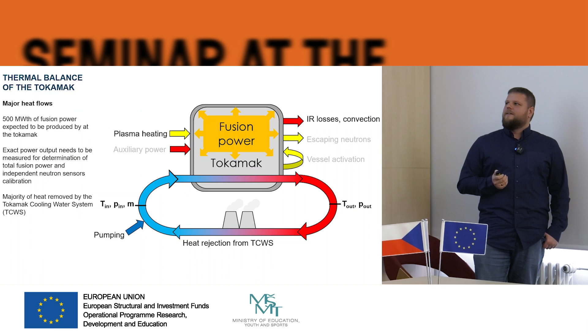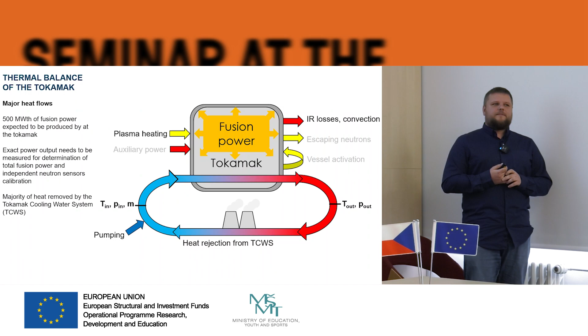The accuracy of neutronic sensor measurements decreases with time, and they need to be calibrated sometimes. In fission power plants, this is done with exactly the same system. You have a completely independent system which gives us the value of power output of the reactor. By comparing this power output with the output of neutronic sensors, integrating them over the pulse, we should be able to check for the drift of neutronic sensors.